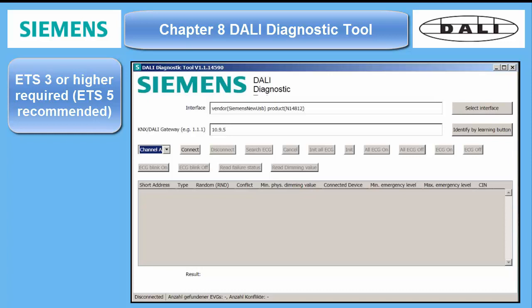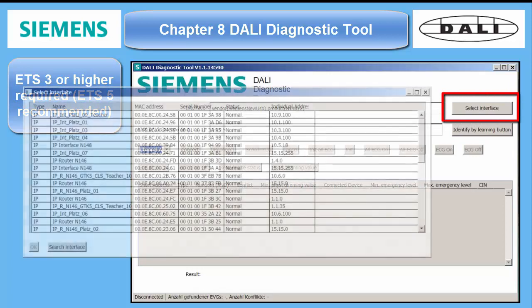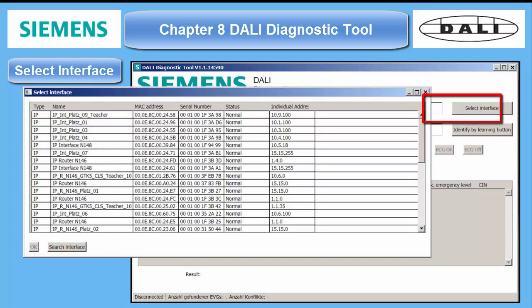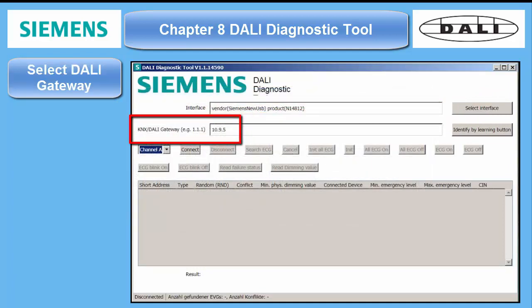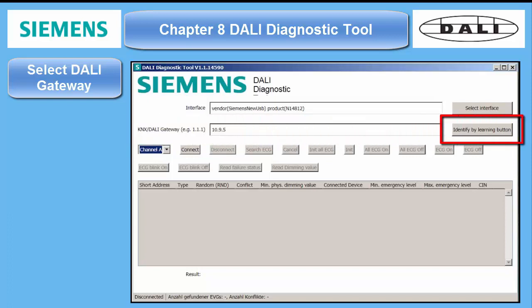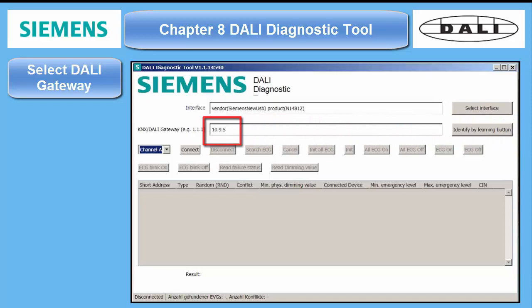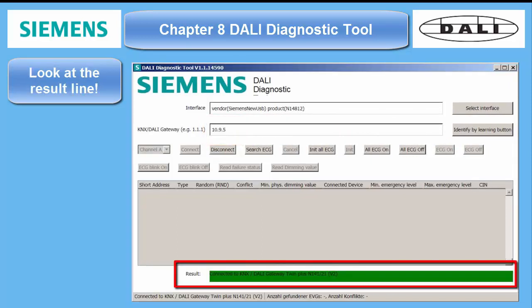The workflow to establish communication with the DALI bus is simple. First, you select one of the interfaces, which you can see when you press the button 'Select Interface.' The next step is the selection of the corresponding DALI gateway. If its KNX physical address is unknown, it can be retrieved through the well-known procedure by pressing the device's program button. Otherwise, you enter the physical address directly. Note the result line — it will always tell you what the tool has done before.